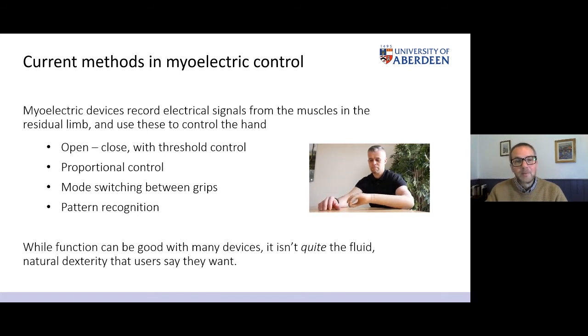If you are lucky enough to have a multifunctional device that has the potential for using different grips, then those 2 signals are not going to be enough, because you have to not only open and close the hand, but you have to tell it which grip you want to be controlling. So it might be that you do some co-contraction or a double clench or something like that to switch from one mode to another, to move the hand fingers versus moving the thumb, for example. And there are some developments in pattern recognition whereby you might have more than 2 electrodes, so you might have 5 or 6 electrodes around the interface between the socket and the residual limb. Then there's a controller which recognizes the type of grip you're trying to make by learning the patterns that you make with those contractions across those muscles.